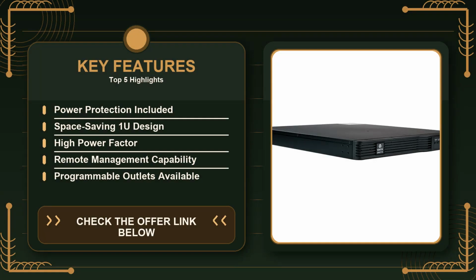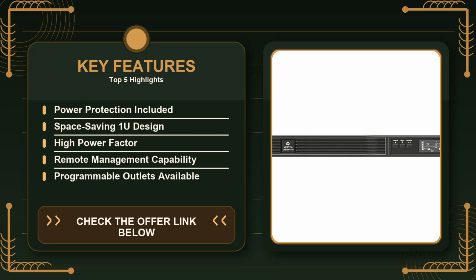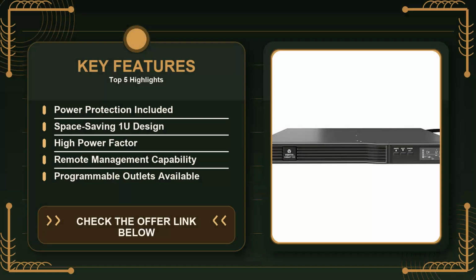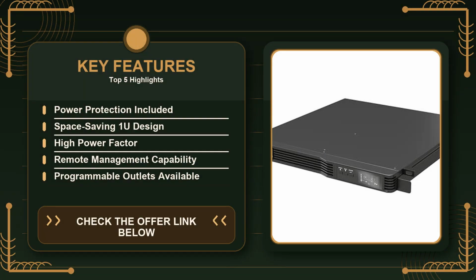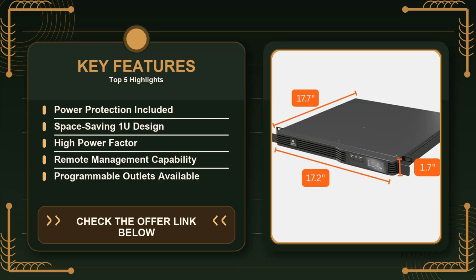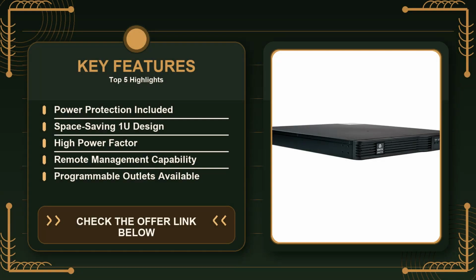But there are practical weaknesses too. The line interactive AVR is decent, but it's not a full double conversion design, so during severe voltage sags the output voltage may still drop slightly. Most users won't notice this unless they have particularly sensitive equipment that demands a perfectly stable sine wave, for example, high-end audio production gear or certain legacy medical devices. In those cases, a true online UPS would be safer, albeit more expensive and larger.